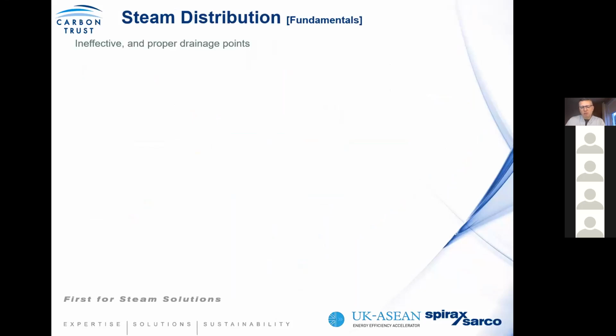Now, when we said we want to generate high quality steam, remember, steam will want to release its energy as soon as it comes in contact with a system or process, or even a distribution system at a lower temperature. So we call this distribution losses. Within your steam system design, you need to basically counteract this process by ensuring that you have effective condensate removal throughout your distribution system. Because, again, the steam will want to release its energy. It's an inherent feature of steam. And a lot of the problems we're coming across is that there's ineffective consideration towards condensate removal, mains drainage, and an effective steam distribution system. So we're going to go through a few different pointers of what we call worst in class and best in class. And this is based on system findings.